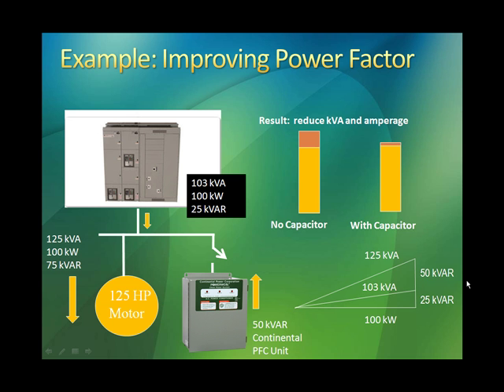Now let's take a look at this from a real-world example. In the upper left you see a picture of what's called a switchgear. This is a three-phase typical large main distribution panel in a commercial facility. And we have, in this example, a 125 horsepower three-phase AC motor. If you look in the bottom left, you see what that motor requires. Remember, we talked about the various terms. 125 kVA, that's our apparent power. 100 kW, that's our working power. And 75 kVAR, which is our reactive power, or useless power maybe. That's the power that's needed to magnetize the windings. Now, we have a PowerWorks there. This is a 50 kVAR Continental Power PowerWorks unit, which provides power factor correction amongst surge and spike protection and noise filtration.